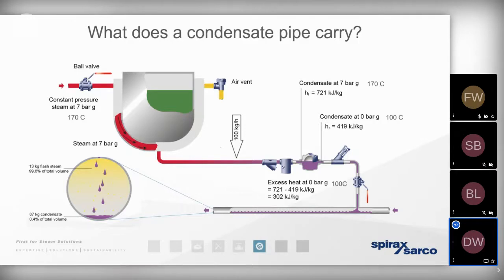handle it correctly. So if we look at a typical steam using process, we know that when steam gives up its heat energy, it condenses. It changes state from a gas to a liquid. So if the process is calling for a mass of 100 kilograms per hour of steam at 7 bar gauge, 170 degrees, well, we know the condensate is going to exist at 7-bar gauge, 170 degrees, and at the same mass, 100 kilograms per hour.